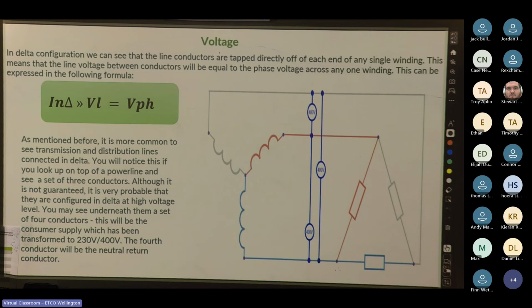So it's more common to see transmission and distribution lines connected in delta. You'll notice this if you look up at a power line: you'll only see a set of 3 conductors for the most part, although it's not guaranteed. It's very probable that they're configured in delta at high voltage level. You may see underneath them a set of 4 conductors. This will be the consumer supply, which has been transformed to 230 or 400. Although obviously if you live in an area where it's all underground, you'll see nothing. Cool. So the 4th conductor will be the neutral return. The most important part to remember about this is that voltage line and voltage phase are equal.